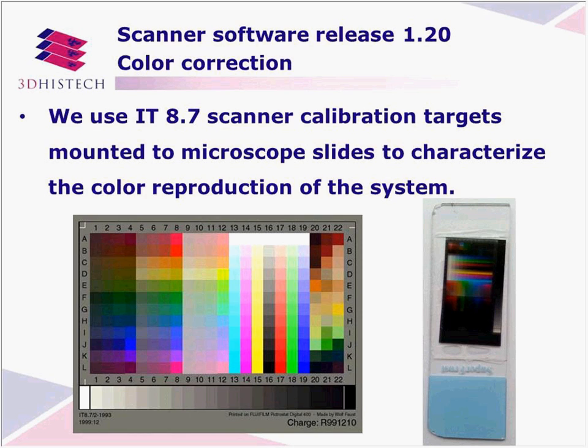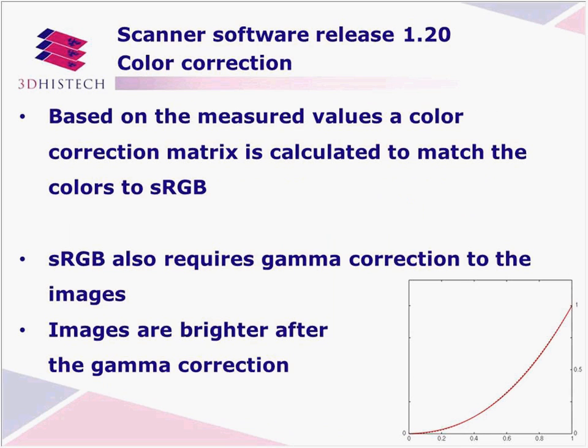So this IT8.7 scanner calibration target looks like you see on the left. This is an ideal computer generated image, so you see how many color spots and grayscales are embedded in the standard, and on the right you see how this target is actually mounted on a glass slide. So the glass slide has to be scanned. Then the special calibration software calculates the color correction values. Based on these values, the color correction matrix is calculated and applied to every field of view.